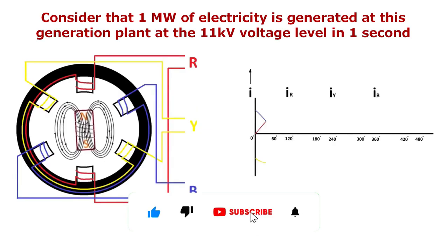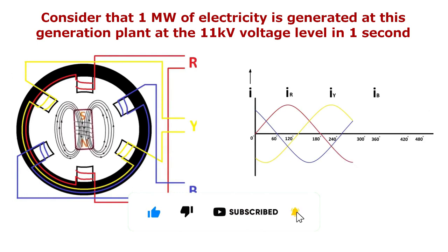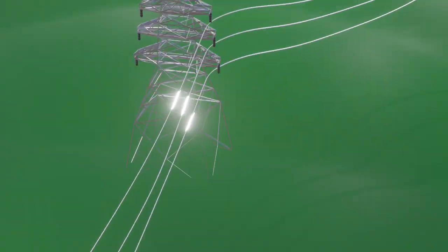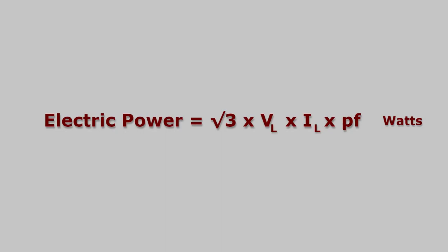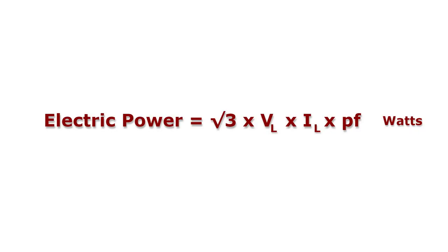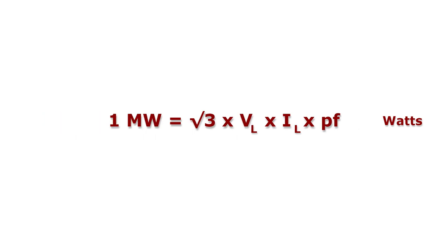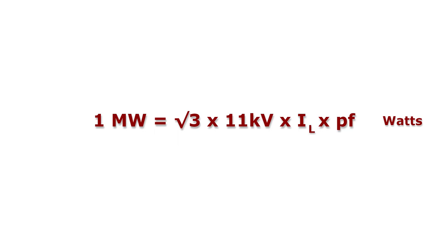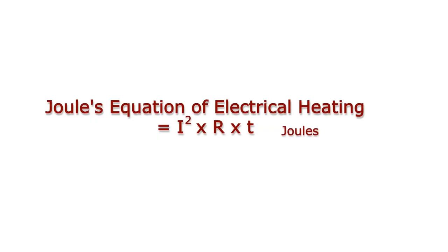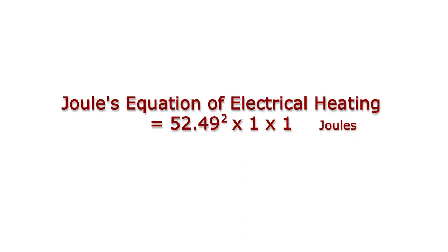Case 1: consider that 1 MW of electricity is generated at the generation plant at the 11 kV voltage level, and the same power is supplied to consumers at the same 11 kV voltage level without stepping up the voltage. Using the formula for electric power — watts equals root 3 times line voltage times line current times power factor — the current flowing through the transmission line is 52.49 amperes. Using Joule's equation of electrical heating (I²RT), with resistance R of 1 ohm and time T of 1 second, the loss due to heating equals 52.49² × 1 × 1, which is equal to 2,755 joules.